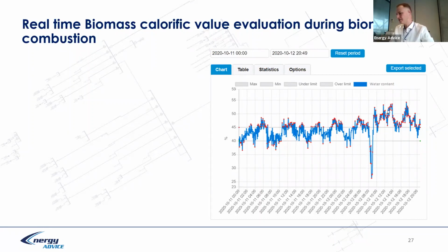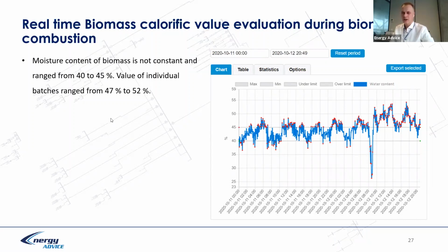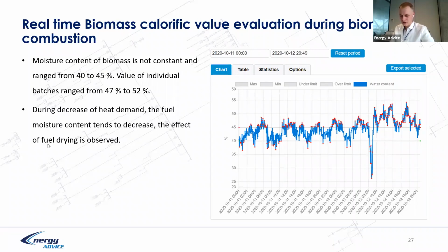And you can see variation of the fuel content over time, starting from 40%, coming to 45, 40, 45, so it's not stable. And because fuel water content is not stable, calorific value is not stable, and the automation control system is controlling the fuel amount according to the commissioning engineer's set points from commissioning time, and probably with some amount of fuel at that time, when the commissioning engineer built the boiler automation and you run it, the boiler entering operation. So this effect cannot, in fact, be controlled by the control system.